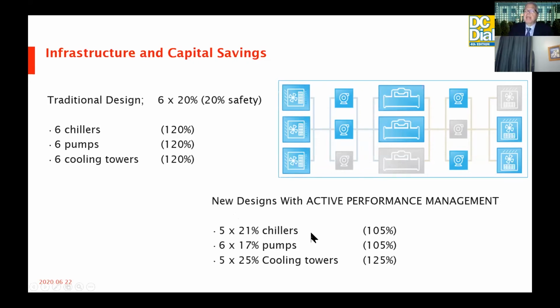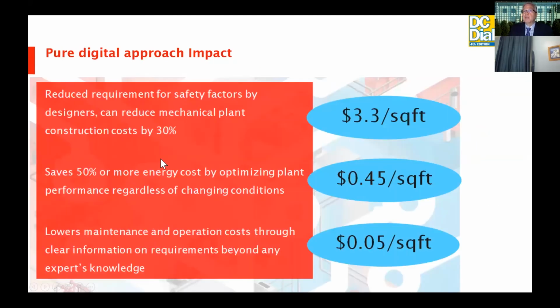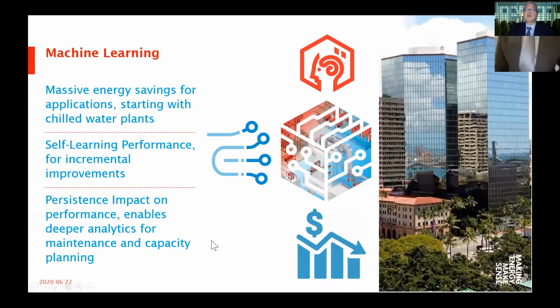And this is what's making some of the smaller and medium-sized district cooling plants more viable economically, because we're reducing the original investment, somewhere around $3 per square foot served. We're improving the OpEx by about 40 to 45 cents per square foot, and lowering maintenance costs, the overall maintenance cost for these systems being reduced by about 5 cents per square foot served.